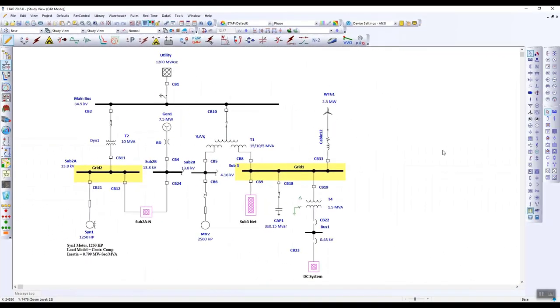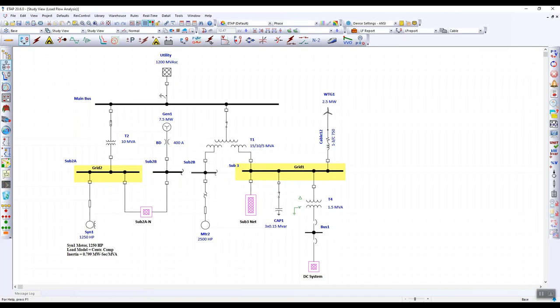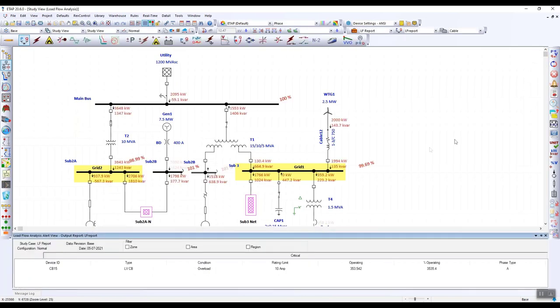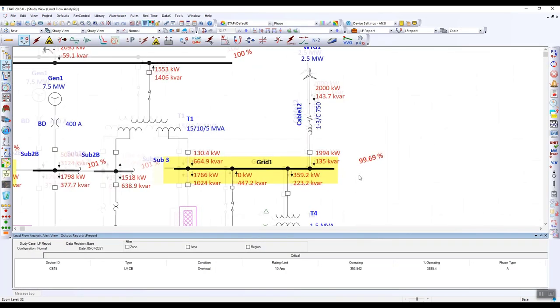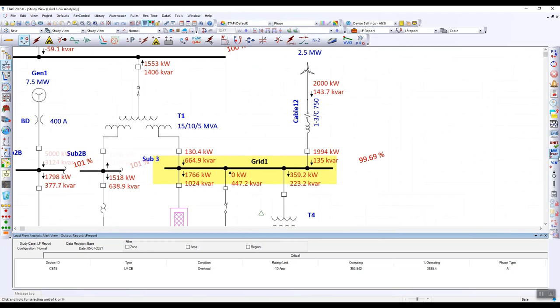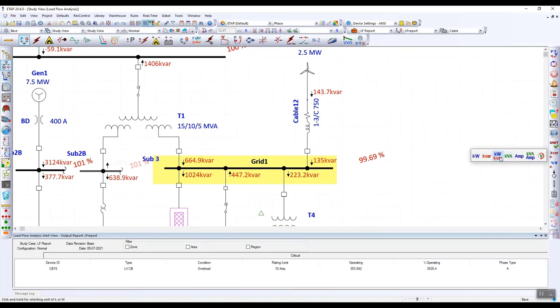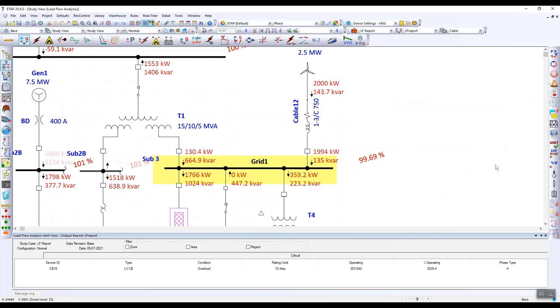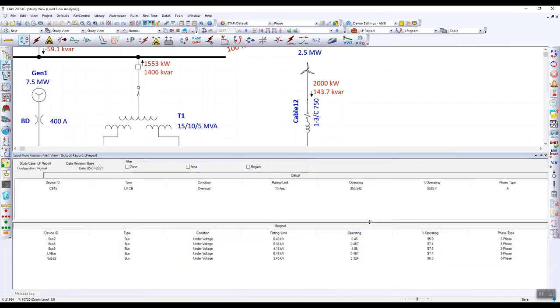Here I have opened another pre-built project that already has all the device rating information filled out. I'm going to run a quick load flow calculation. You'll see the various real and reactive power flow results populated on the single line as well as the voltage percentage at each bus. We can also change the units to show the real power only, reactive power only, apparent power, current, and apparent and current as the units showing on the single line.